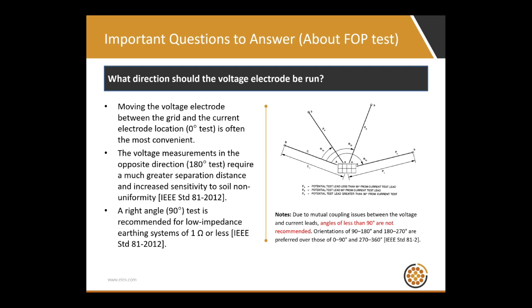The reason for that is that usually we need to set up some sort of temporary easement where we have run the current leads and set up the current electrode. So it's most practical to run the voltage measurements in the same direction, but that can lead to inaccuracies, as we will see. You can also run the voltage measurements in the opposite direction, 180 degrees away from the current electrode.